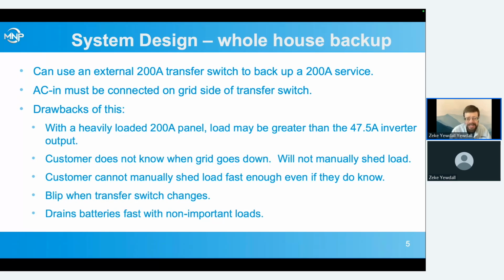And of course, it drains the batteries quickly with non-important loads, versus having them on smart loads where you can set, if the batteries are full and it's a short outage, or if the sun's out, keep running some big heavy load, or in a less important part of the house. But as soon as the batteries drop to 80%, dump some of those and keep that power for more important stuff. You can do that when you've got it wired in on backed up loads panels using the smart load breakers, but not so much when you're just backing the entire house up.